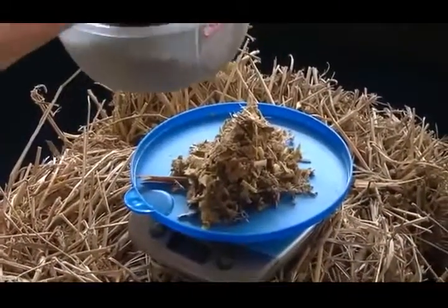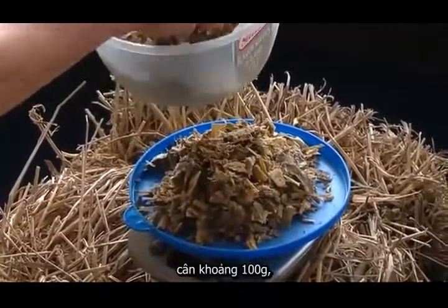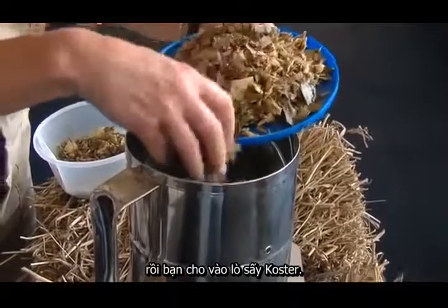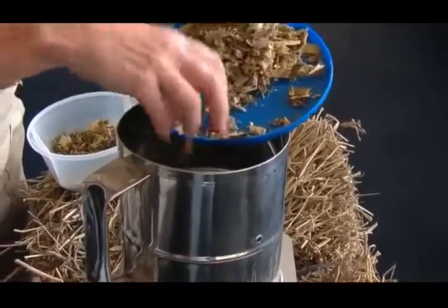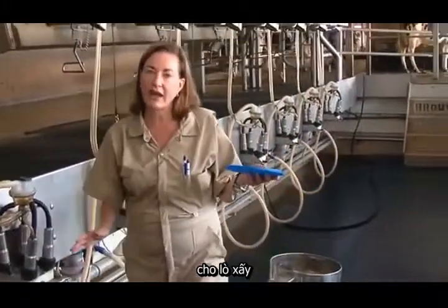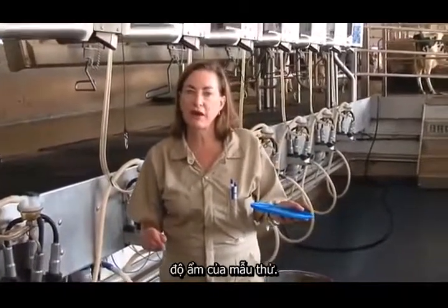The procedure is this: you take a fresh sample of your product, weigh out about 100 grams, and then you simply put it into the Koster oven, turn the oven on, and you leave it to dry down. The drying down of course will be determined by how much moisture is in the product.